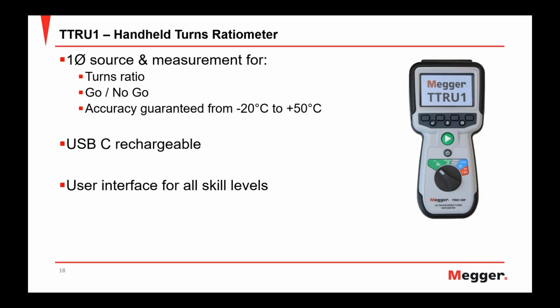They can easily pick it up, along with the automatic result saving of the device that will give you reports when you export to Excel, or that optional 2-inch printer. I've seen people tape those up inside cabinets at the end of testing. It really allows the user to have the confidence that they've, again, set up the test properly by comparing the nameplate vector directly to the vector that's on screen, with the clear test setup with the connection labeled right there, and then the clear results evaluation.